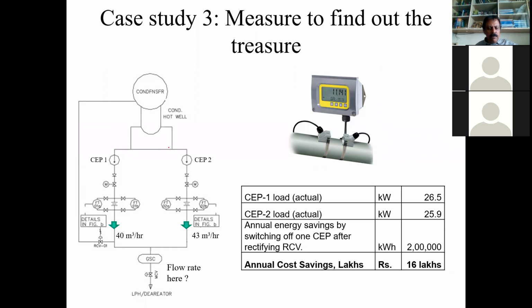This is another interesting case of how measurement can help in identifying some of the losses. This is a gas turbine power plant, a 32.5 megawatt combined cycle power plant. On the steam side of the power plant, we have the steam turbine dumping the steam in the condenser. We are circulating the water, and the condensed steam, or the condensate, is coming to the hot well. From the hot well, you have condensate extraction pumps which are pumping the water to the deaerator. So there are obviously two pumps, CEP1 and CEP2, condensate extraction pumps.